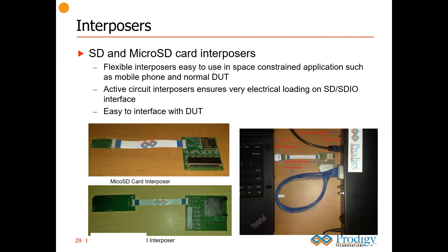Okay. Now, once we have these high-speed signals, 200 megahertz, they move from the test point all the way to the hardware inside the protocol analyzer. These signals are NRZ signals, but they're not encoded so much, so the frequency components of these signals can be quite different. Because of that, the propagation delays for the command, clock, and data lines can vary. In order to address those two challenges, we have provided an auto-tuning feature within our protocol analyzer, where you run your data, and the protocol analyzer will try to identify the right sample point where the CRC errors are minimum, and then it will set the tap values within the analyzer so that we are sampling the clock, command, and data signals appropriately without any problem.